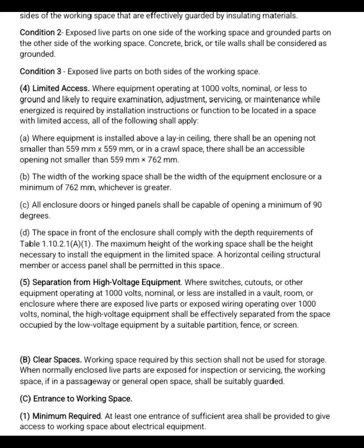Separating from high voltage equipment. If low voltage equipment is installed in the same room as high voltage equipment, they must be separated by a partition, fence, or screen to keep workers safe. In clear space, the working space around electrical equipment cannot be used for storage. If equipment must be opened for servicing in a hallway or open space, it must be guarded to keep people out. In entrance requirements, there must be at least one safe entrance that allows easy access to the electrical equipment and its working space.